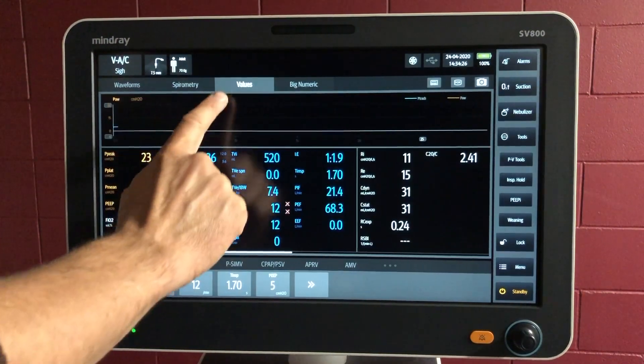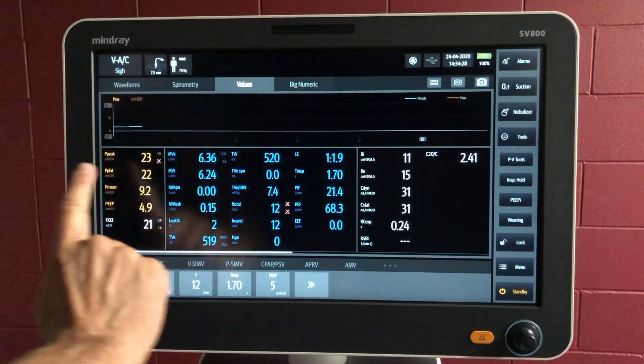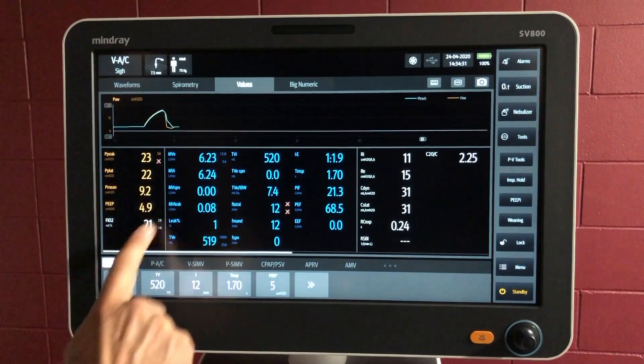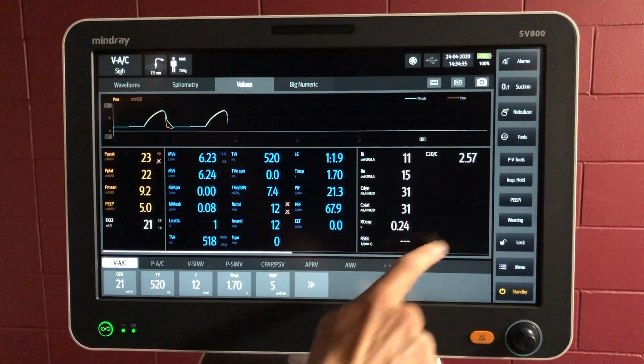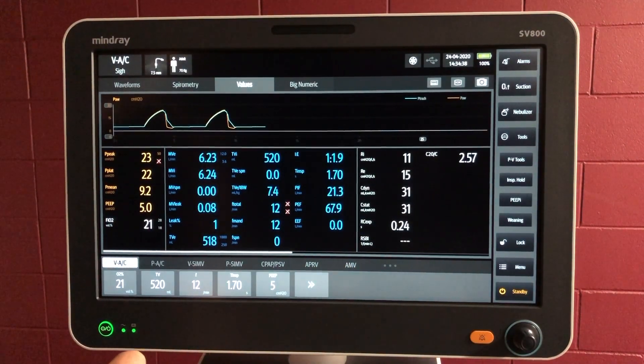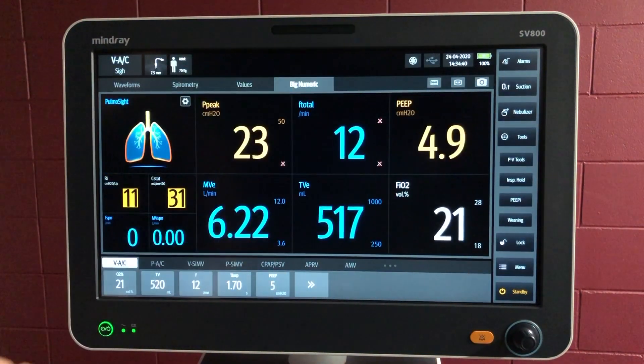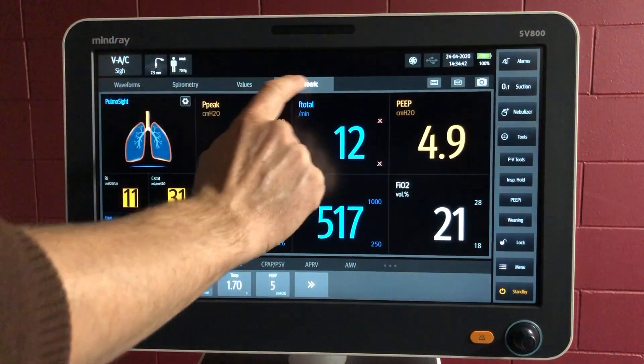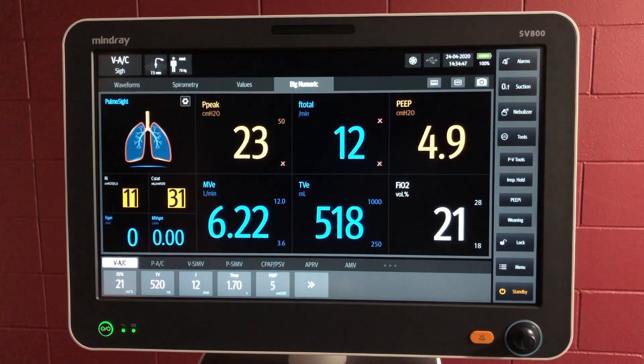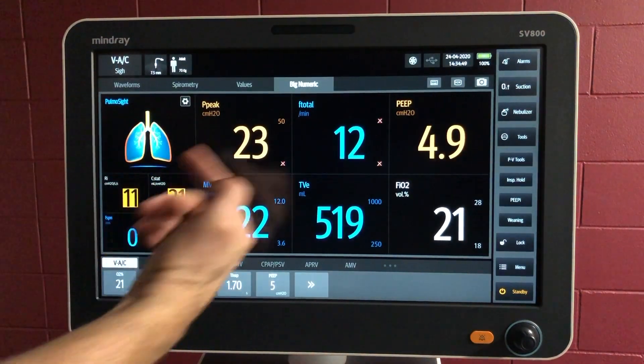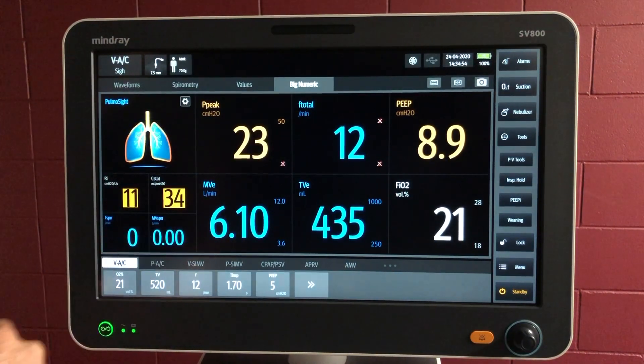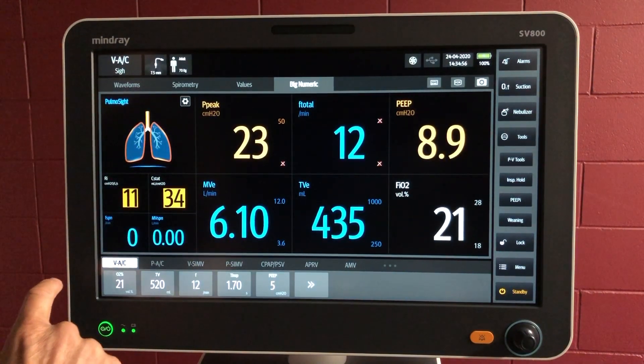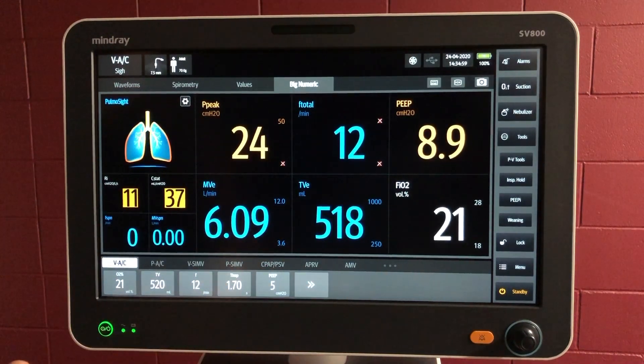The values tab at the top gives you all of your readings — again, the orange are the pressure, the blue are the flow, and here's some calculations. The big numeric tab at the top gives you a large font of your basic readings: again, orange for pressure, blue for flow. It gives you the PulmoSight as well, and as per usual you've got your settings underneath.